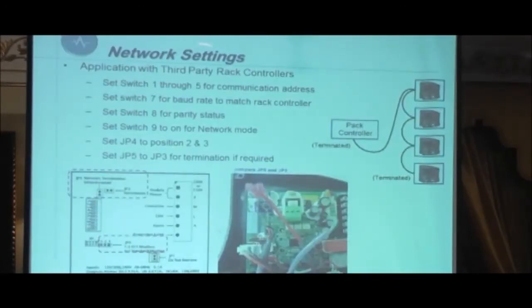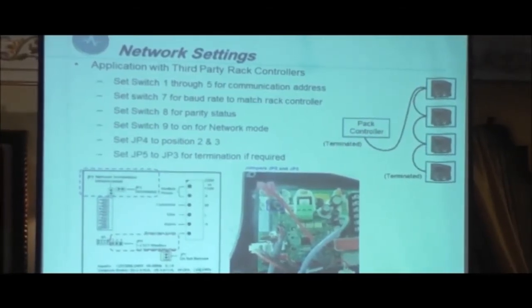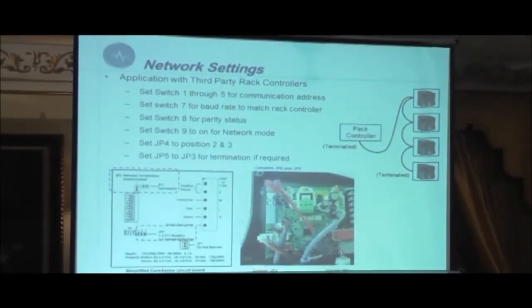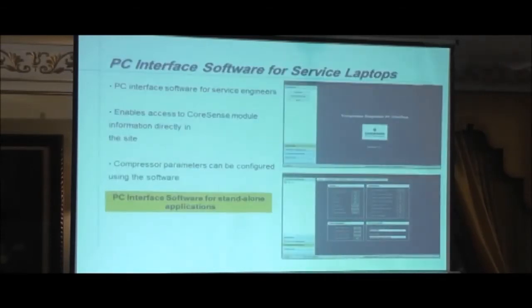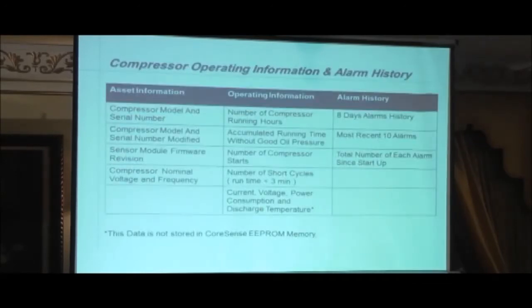So this is an example of a network where you have a rack. So you go from compressor 1 to 2 to 3, 4 to the rack controller. Right. Typically this rack controller will be connected to a monitoring server. So all that information will be available on the server. Now, if you choose to use a PC to extract information from the compressor, after you've connected it, this is the software that will come up on your laptop. Right? It allows all access to the compressor parameters.